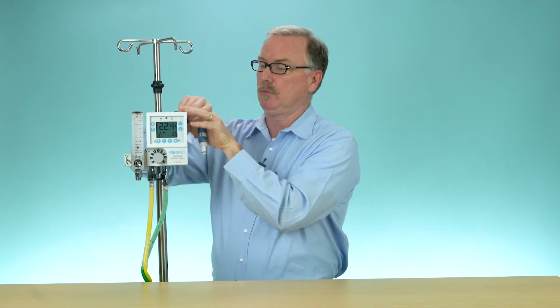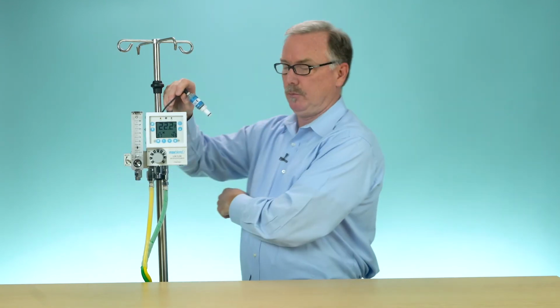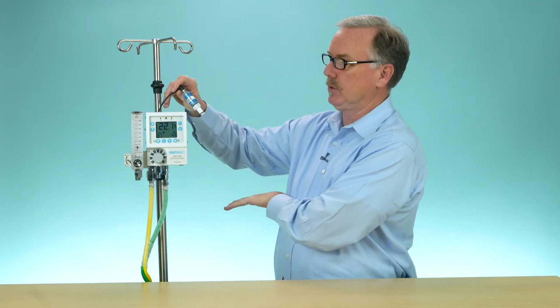So let's say I have an oxygen flow meter, I have a connecting tube, maybe a clean glove. Put my fuel cell in the glove. I flush the glove with that 100% gas source. Calibrate. Didn't interrupt patient care. Calibrate's complete. Pull it out of the glove. Turn my wall flow meter off, which was a 100% gas source. Put my sensor back in. Did not interrupt patient care, and I met the one requirement of a 1-point cal at 100%.